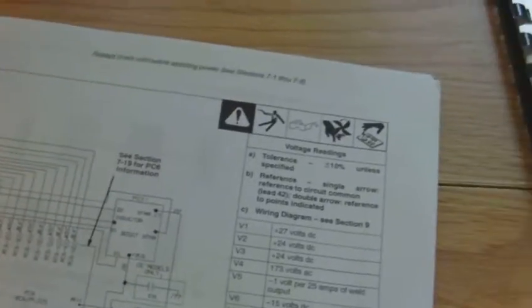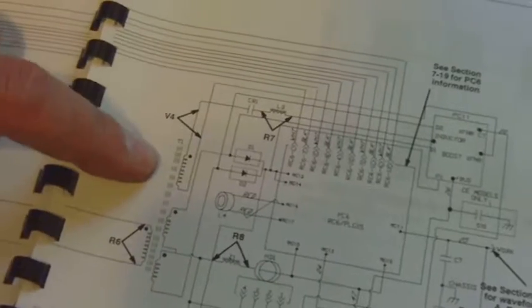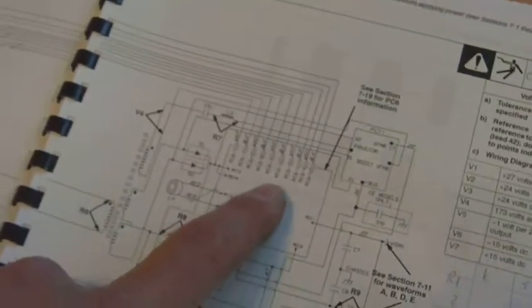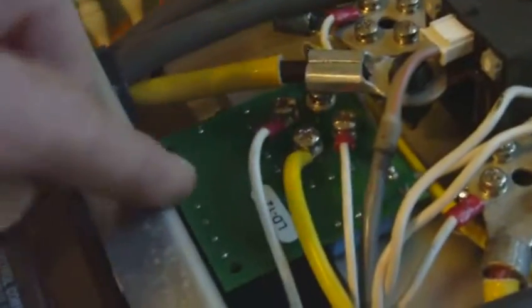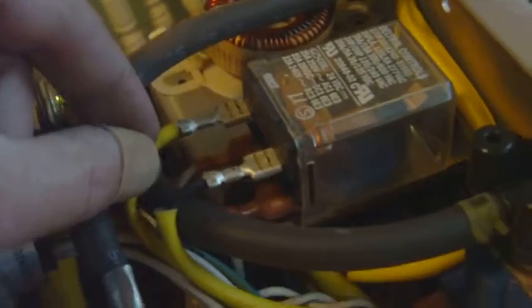V4 is on the other side of the machine. That is a secondary winding off of the main transformer, which is the guy back in there with purple. So hold on a second. Okay, so V4, here we have the main transformer back in there. V4 is a secondary winding that provides 173 volts AC to what? PC6 is the boost circuit, which is this guy over here. That's the boost board. So one end of that winding is here on the relay contactor. The other end is over here on the boost board with this guy. Should be 173 volts AC. I get nothing.